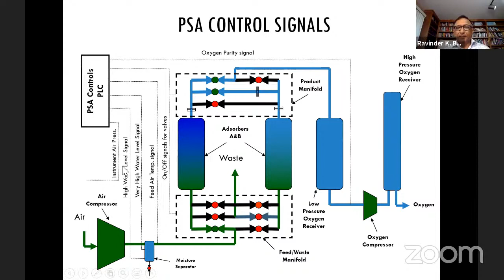A typical layout, if the plant is not very large, specifically for hospitals, would look like this. The PSA plant is not really that big, around 2 tons per day, which is typical for a hospital's use. We'll have a mechanical room where we put all these things, and it's good to go.